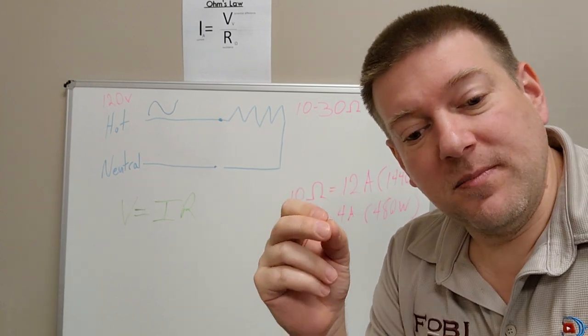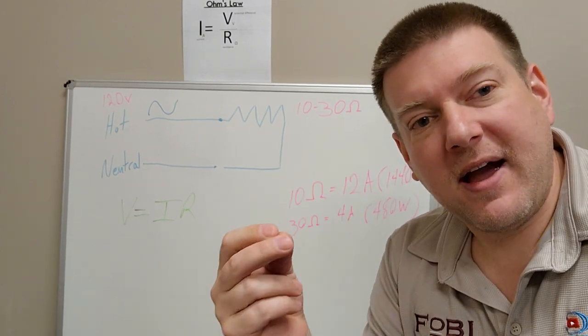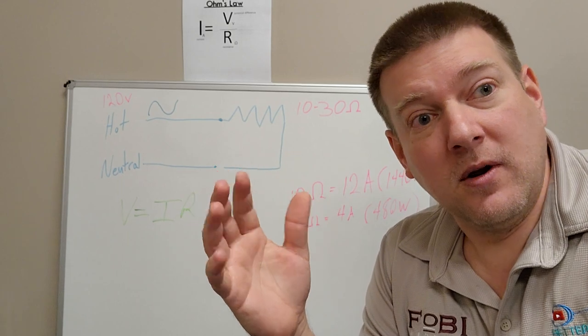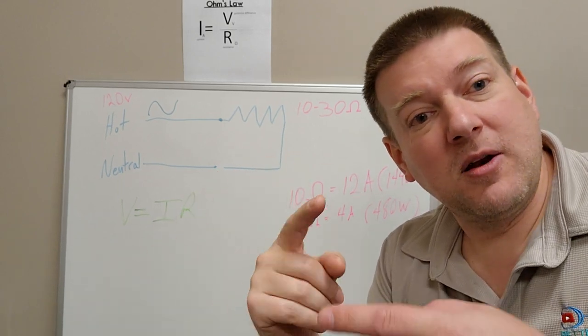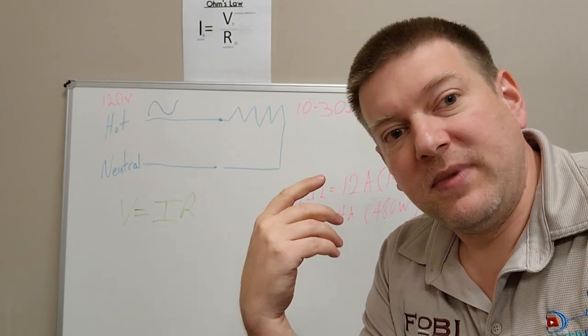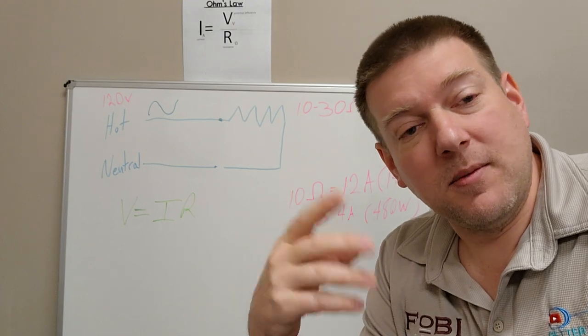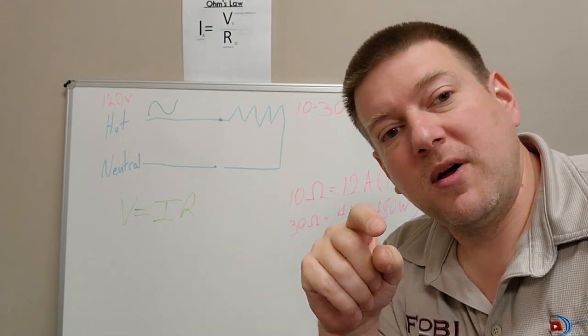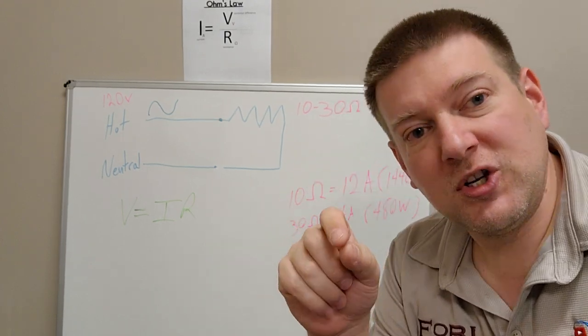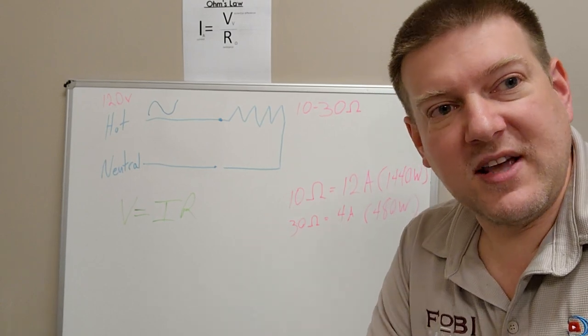Now almost all medical devices have a backup thermostat of some sort. It's either going to be a thermal fuse or another resetting thermostat. Sometimes it's a push button on the back of the device that you push and it will reset it.